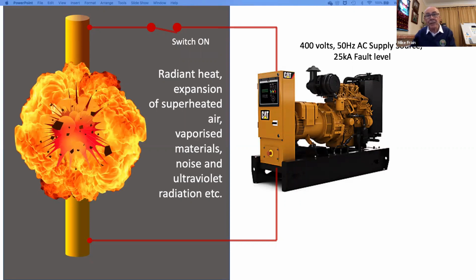What actually happens is that the fuse wire will vaporize, and in doing so, it'll ionize the air between the two conductors, and that in turn creates a low impedance path. Large amounts of current will flow, creating temperatures as high as 20,000 degrees centigrade, so I'm told, which will immediately vaporize any element known to man. There will be massive expansion of air and vaporized conductor material, which causes an electrical explosion. For instance, copper will expand by 67,000 times its original volume in a split second. The thermal effects will cause horrific injuries through burns, ultraviolet radiation, which causes arc-eye, and ballistic effects, which can cause blunt force trauma to anybody stood by.